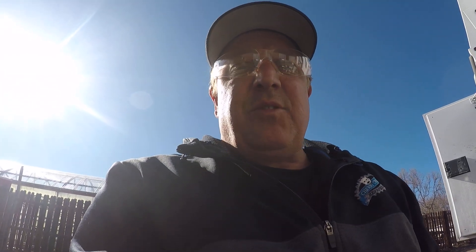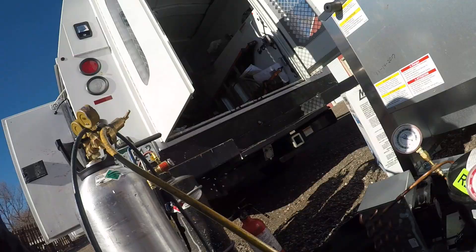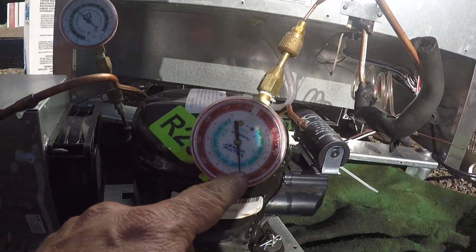I've already previously pressure checked but I couldn't get the pressures right. I couldn't find any soap bubbles anywhere, and I couldn't make the leak detector ring anywhere. So that's how you pressure test — you'll put 200 psi there.